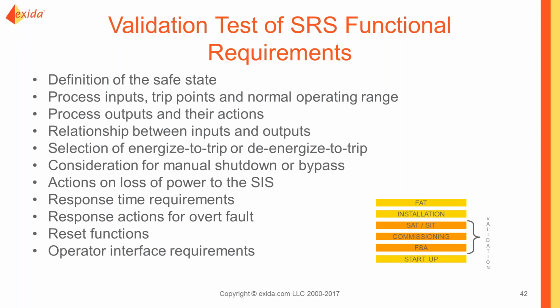Does the final element go to the correct state on loss of power to the safety system? Are the response time requirements met? If there's an overt fault, does it behave as we expect?